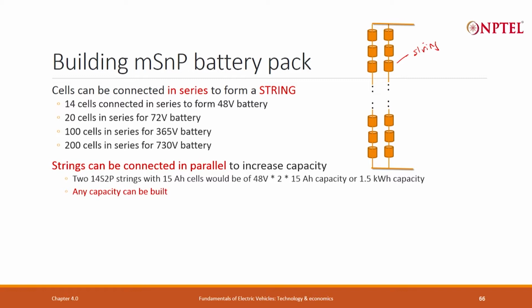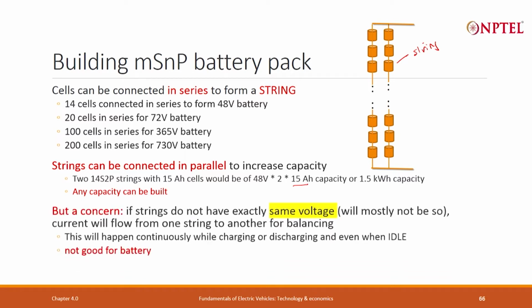Strings can be connected in parallel to increase capacity. So if I use 14S into 2P, or 15 cells, I get 48 volts because 14 in series means 48 volts, into 2 in parallel, each 14Ah, 15Ah capacity. So you multiply 96 into 15 ampere hour, giving 1.5 kilowatt hour capacity. Any capacity, any voltage, any current can be built using something like that.